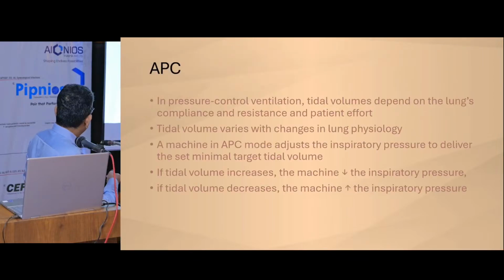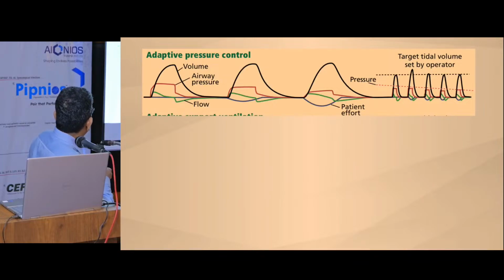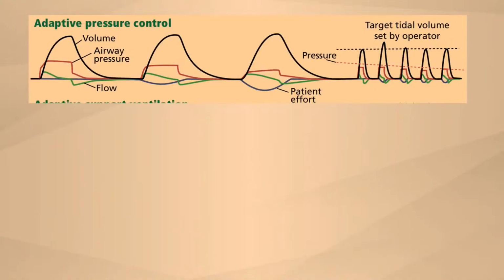As you can see, okay. So, what happens here is, if the patient is not breathing, this is diaphragmatic pull. Okay, you can see in this breath, the patient is not breathing at all. So the ventilator is giving that much pressure, and the volume is set. If the patient is breathing more, the ventilator will reduce the amount of pressure, but the tidal volume will remain constant. So in a normal patient, if the patient breathes more, tidal volume will start going up in a pressure control ventilation. In adaptive pressure control or PRVC, when the patient starts breathing more, the ventilator will give less.